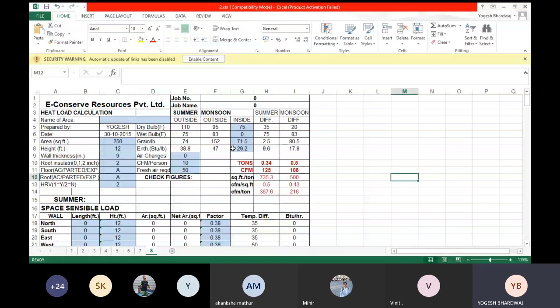So first of all, these are the walls. So we put all the wall area here. All those walls which are coming into the sun exposure are put here. So when you put here, this is the length, this is the height, this is the wall area. Then this is the U factor, which depends upon wall construction. So 0.38 is the value for a 9-inch brick wall with plaster on both sides. This is the temperature difference. So the temperature difference is coming from here only, outside minus inside condition. And here is the heat which is coming from the north wall, south wall. Whenever I put some exterior wall in southeast, it will further add some heat in southeast. So this is the heat which is coming through my walls.